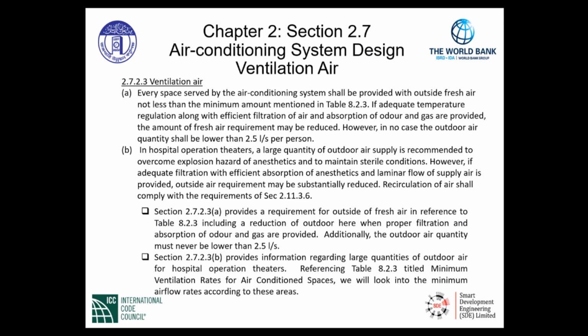In hospital operation theaters, item B, a large quantity of outdoor air is supplied and recommended to overcome explosion hazard of anesthetics and to maintain sterile conditions. However, if adequate filtration with efficient absorption of anesthetics and laminar flow of supply air is provided, outside air requirement may be substantially reduced. Recirculation of air shall comply with the requirements of Section 2.11.3.6.